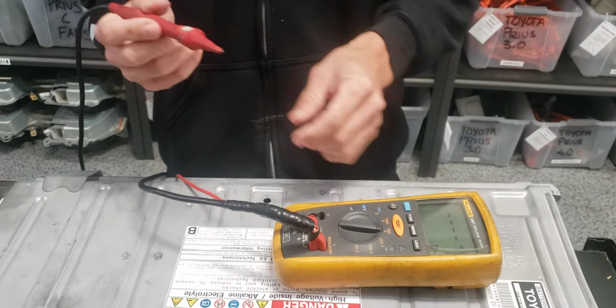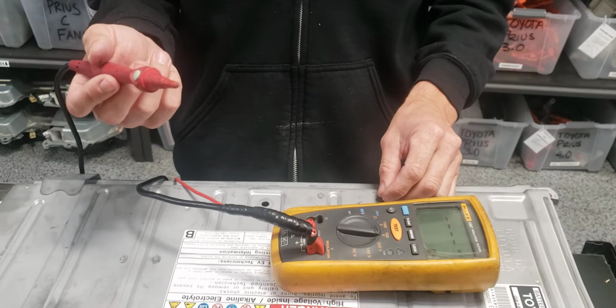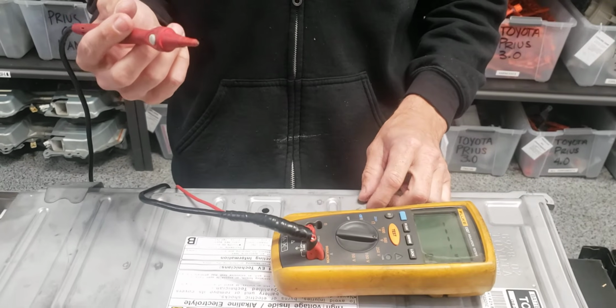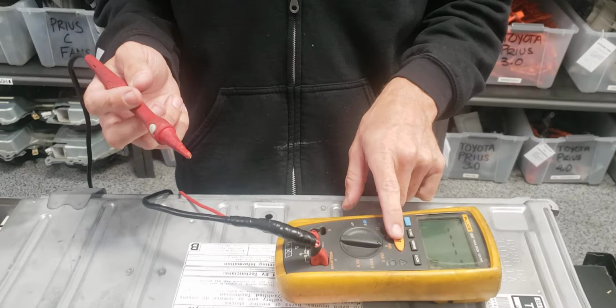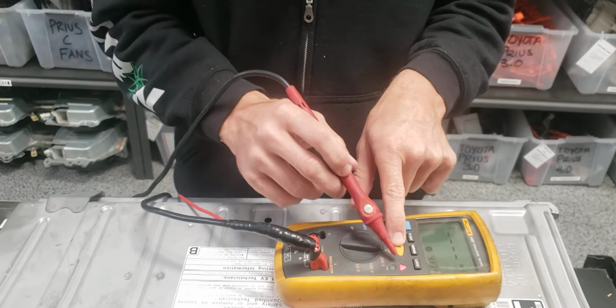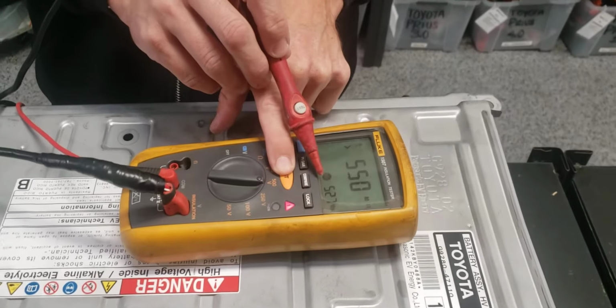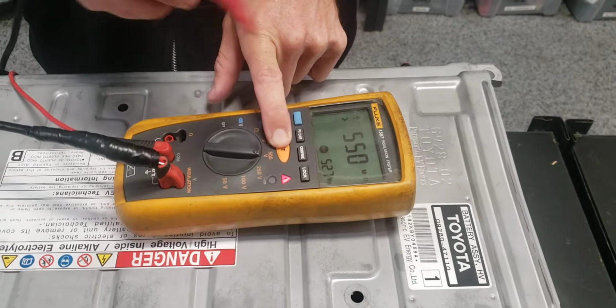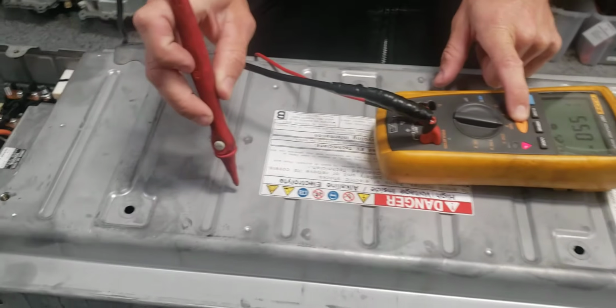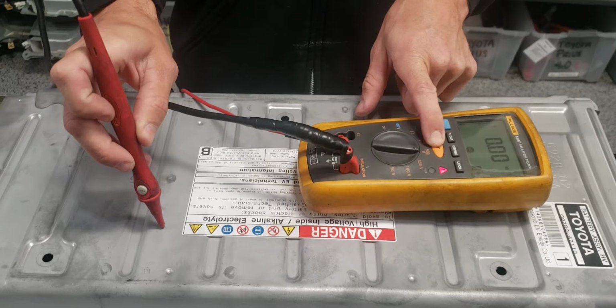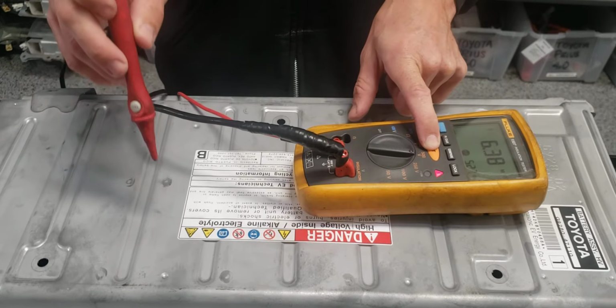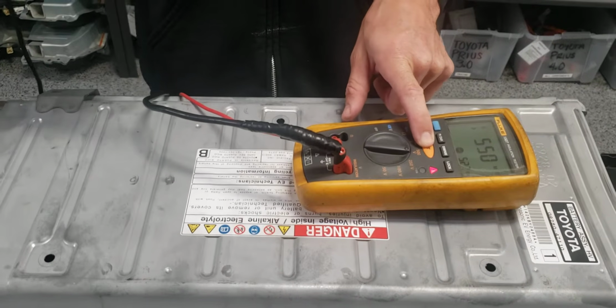Since we have to measure really high resistance, this meter puts out high voltage. It's not enough to hurt you, but you'll definitely get a shock. So I push test, the warning light comes on, it tells me it's putting out 527 volts. I'll test the meter - when I touch this, it should go to near zero, and it does. So it's saying there's pretty much zero resistance from case to case.